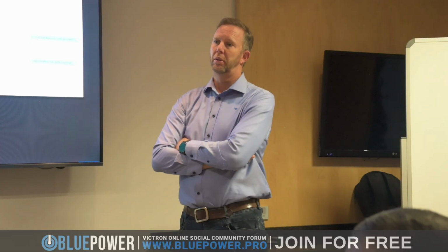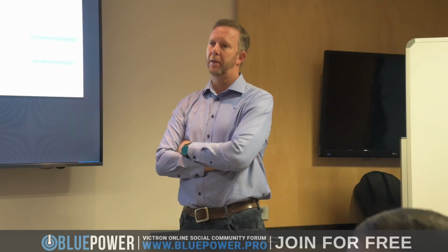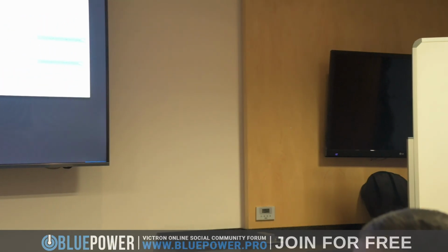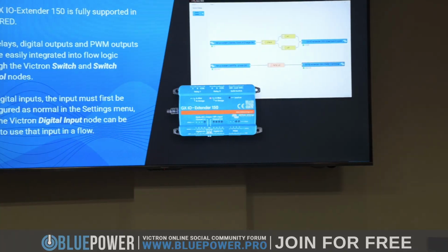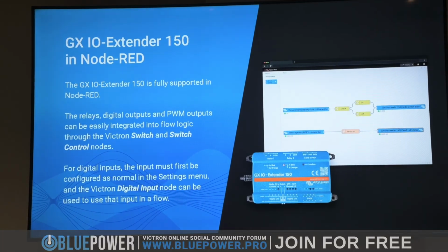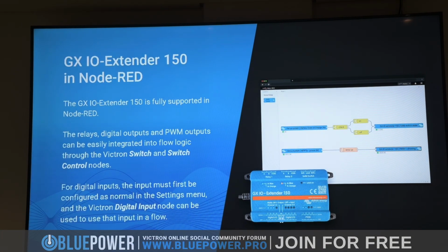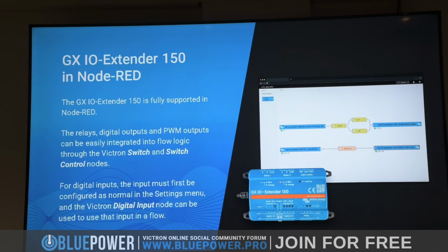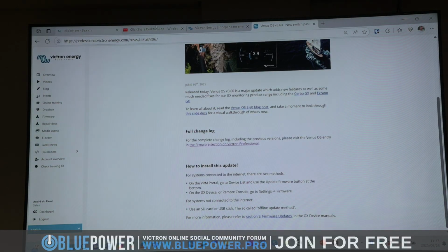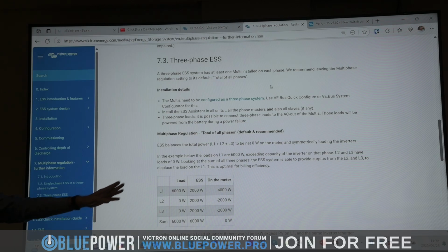The meter, if it's adding all the phases together, it will still show 0. But the Victron will say, well, you pushed back on this one phase, 500 kilowatt hours. Your meter, if it's a smart meter, will actually bill you for that pushing back on phase regulation.